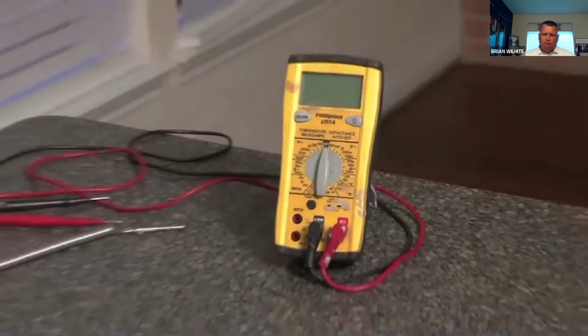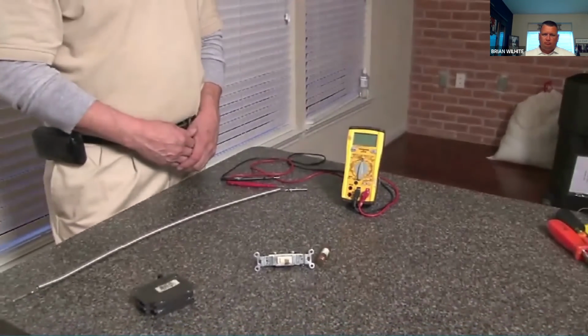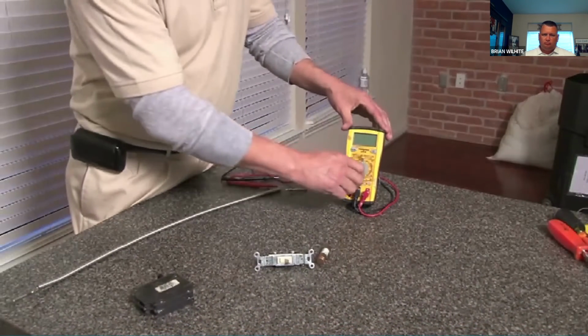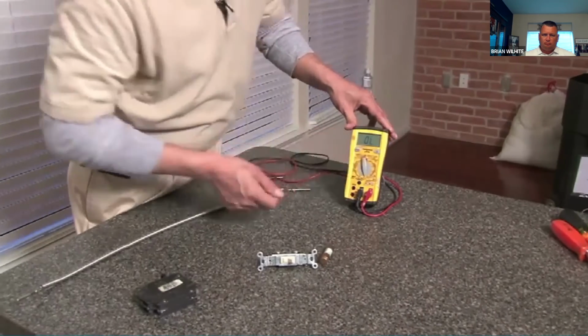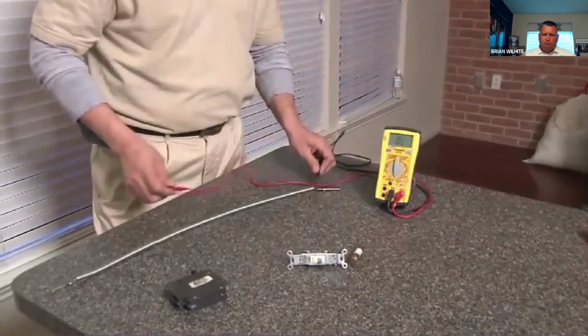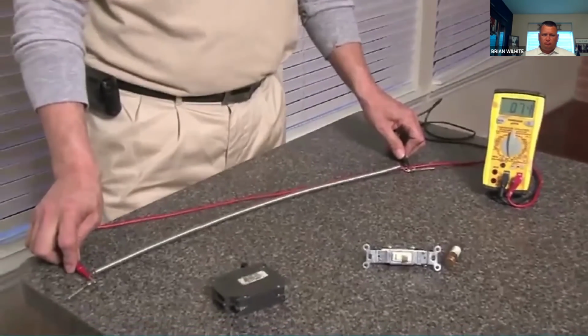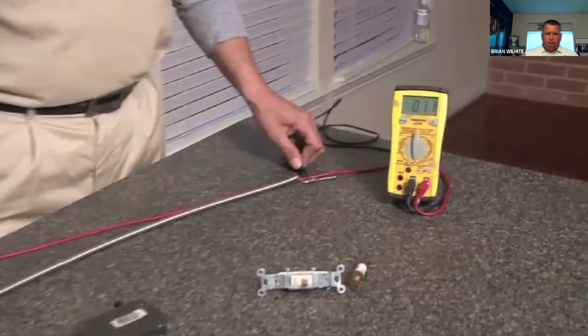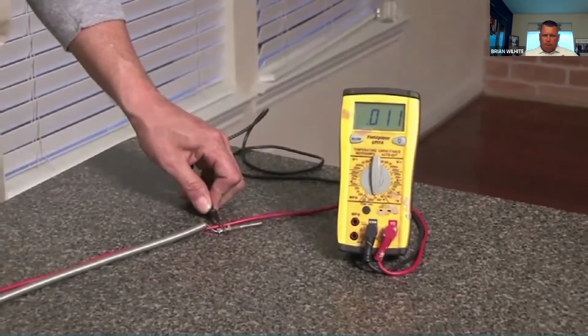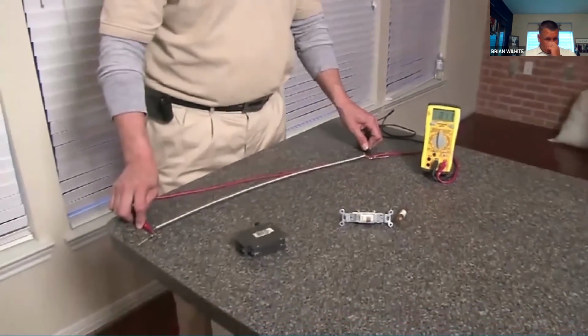Now that we have shown you how to use the multimeter, we're going to show you the difference between continuity and resistance. Continuity is a continuous path between point A and point B. Resistance is going to be in opposition to the flow of electricity, and it is measured in ohms between point A and point B. Our technician is now going to show us how to check for resistance. He's going to use his meter and set it on resistance, and he's going to check the resistance in the heating element. He's placing one side of the meter on one side of the element and the other on the other side, and he's getting a reading of 11 ohms. So this means that element has 11 ohms of resistance and is good.